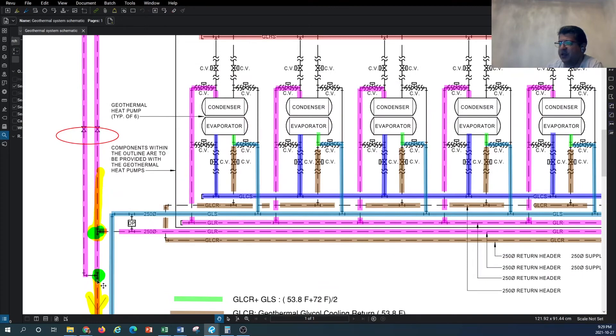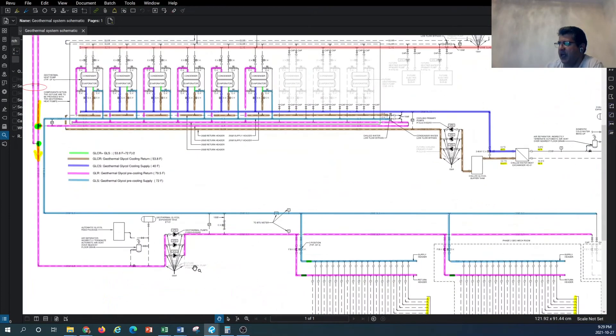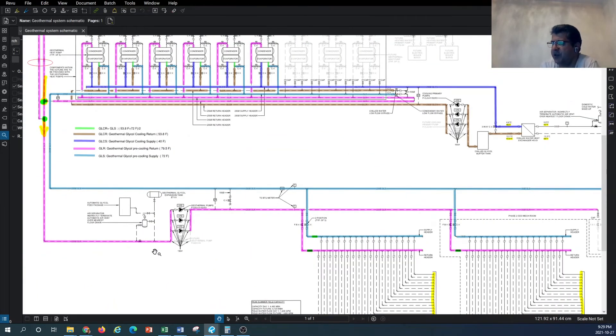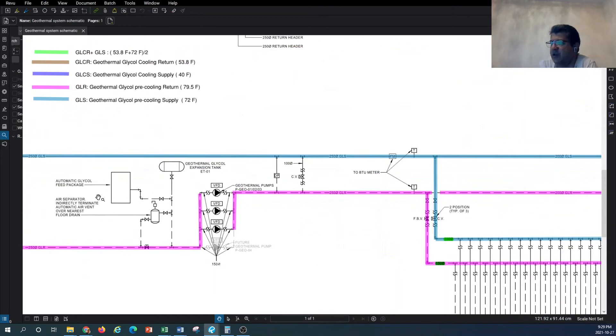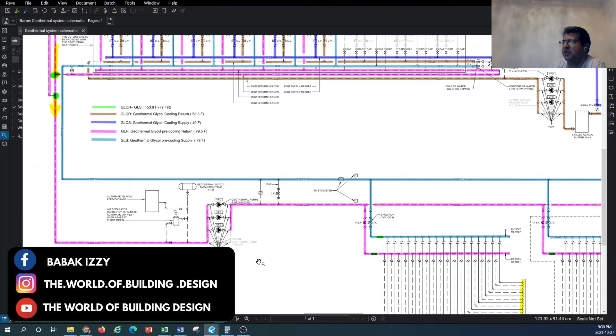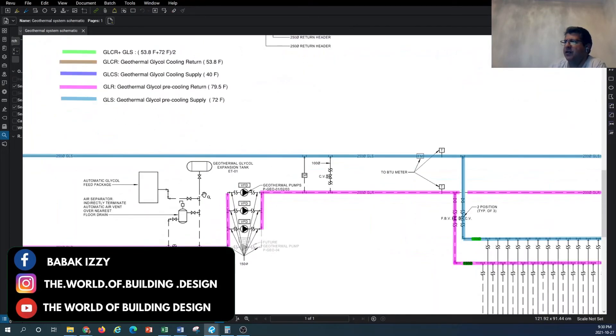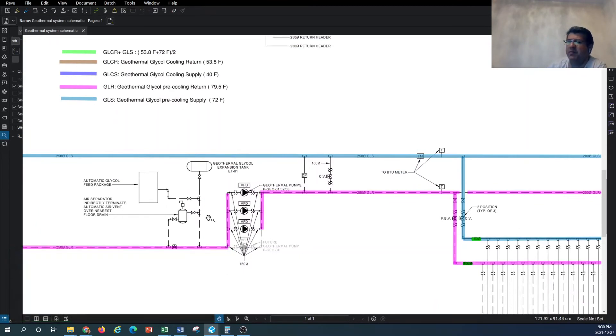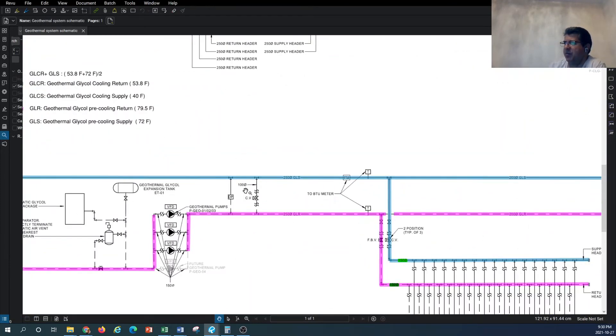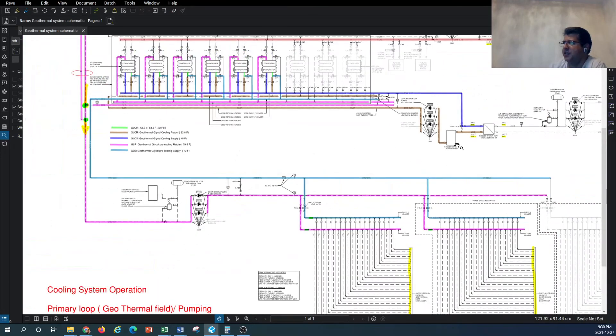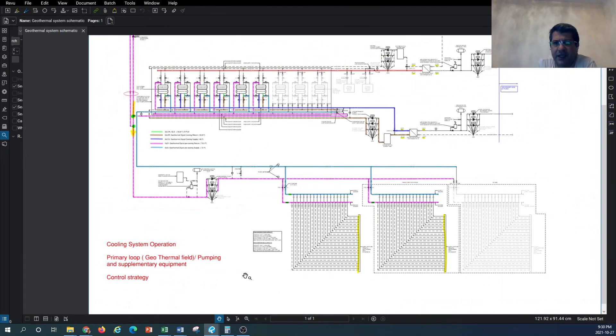There are also typical supplementary equipment items, including an automated glycol feed, since this entire system is a glycol loop that must be protected from freezing during the heating season in winter. We have a glycol mix with the hydronic system on the geothermal side, along with an expansion tank and air separator located upstream of the circulating pumps. There are also differential pressure sensors and other sensors on this schematic, which we will cover in the next tutorial when we focus on the heating cycle.